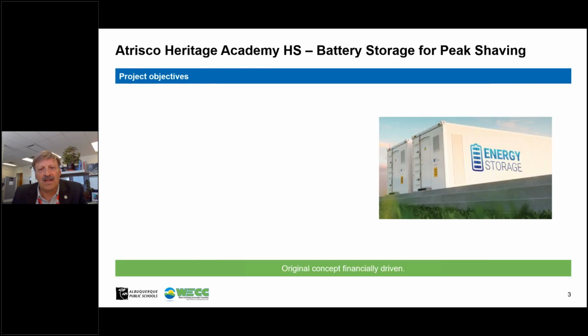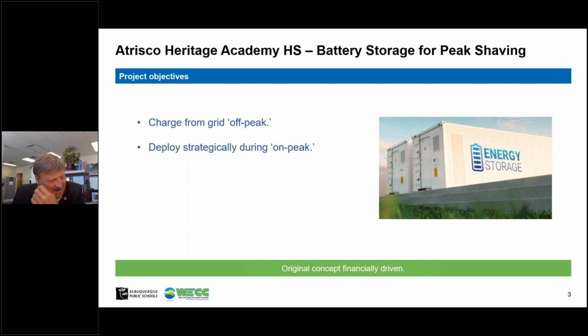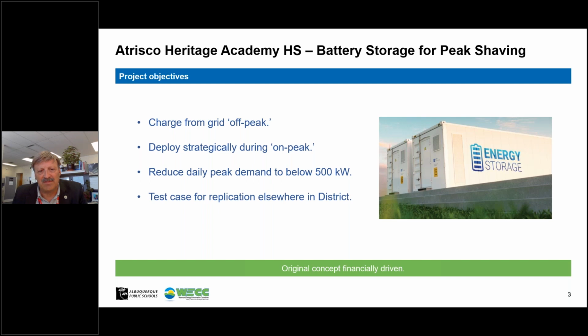So we created a project, a concept to put a battery storage system in there for peak shaving. The typical thing that battery storage would do is charge at night, during off-peak hours, and deploy energy during the day when it was needed to avoid peak. We had 500 kilowatts built into our base utility rate, so we wanted to reduce the peak below 500 at all times if possible.